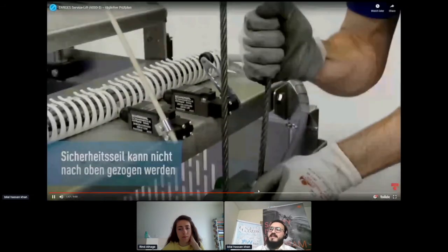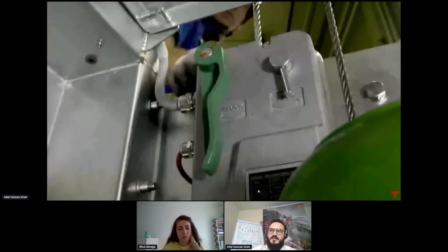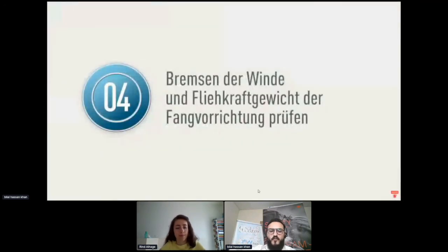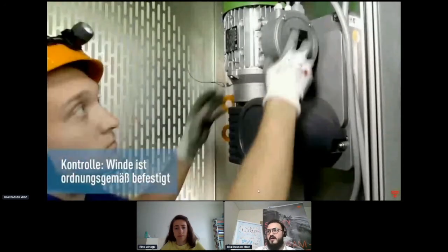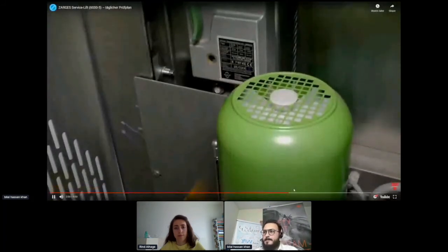Then we have to test by hand, in case the elevator is coming down freely, whether this OSL works or not. By pulling this cable, we check whether this function works, and then we also check the function of the motor and everything. Let me go with it first.